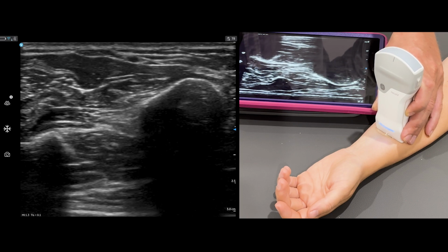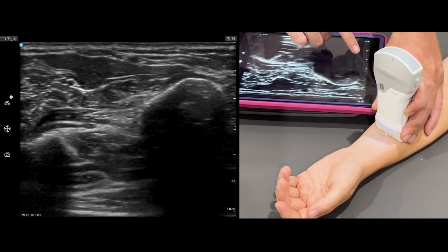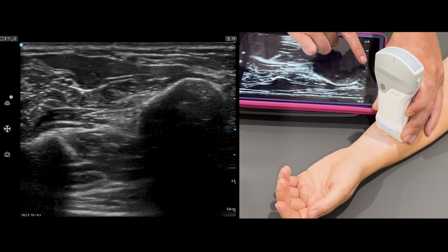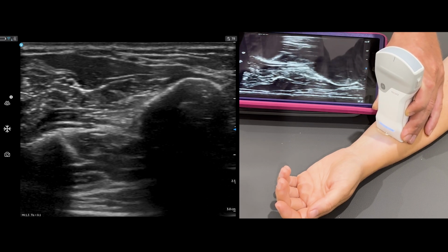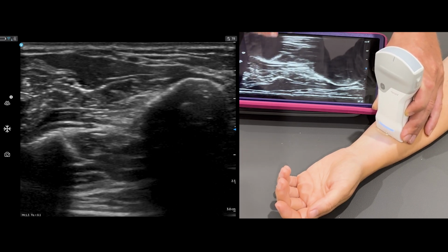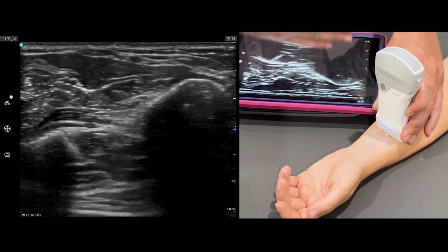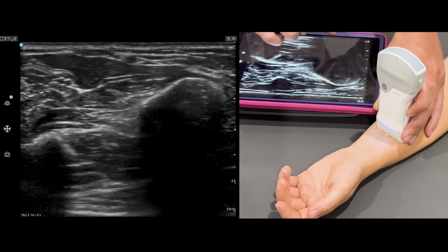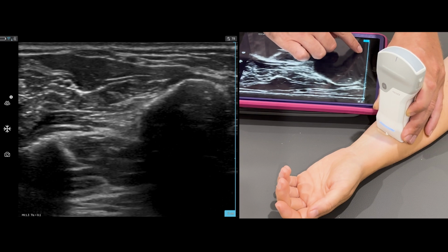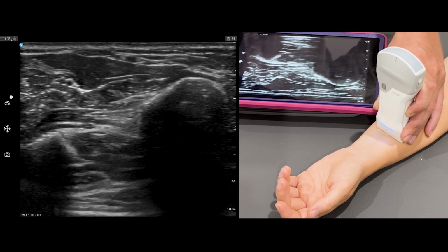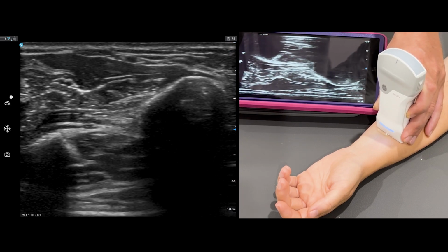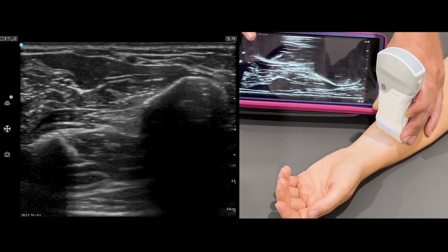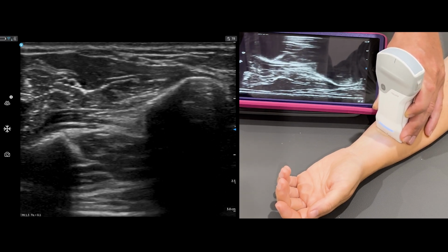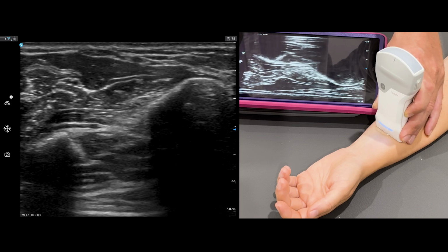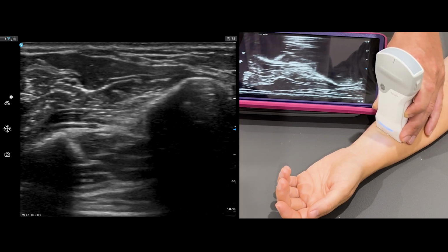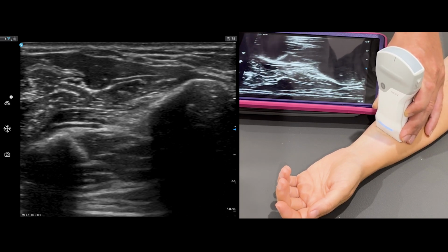There's no specific focal zone that you can adjust, but you can see this blue arrow on the right-hand side is the focal zone. Therefore we will get the best resolution in the middle of the image. So whatever we're looking at, we would just adjust the depth appropriately to get the best resolution we can. So that's the gain and the depth. There is no frequency that you're going to change. That will just alter automatically depending on your depth. I do like to be able to change the frequency, but that isn't something that you can do on here.